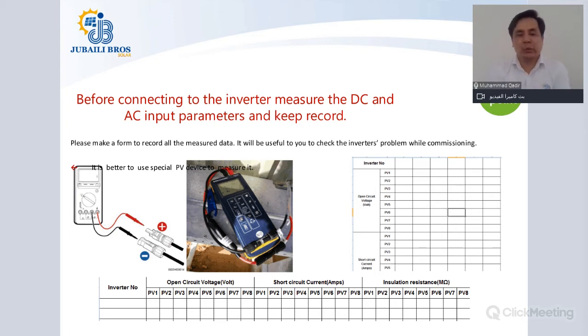So I highly recommend that before you connect your solar cables to the inverter, please measure the open circuit voltage, the short circuit current, and the insulation resistance of all your strings, and then go for the connection, so that once you commission, you are aware that all these strings are connected properly and should be functioning properly as well.